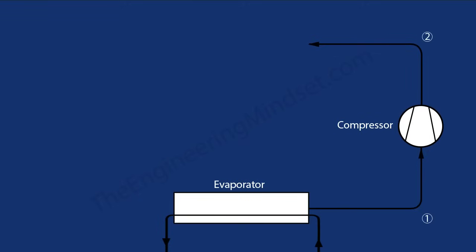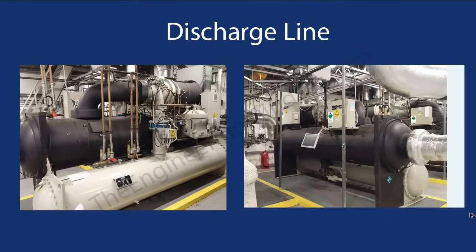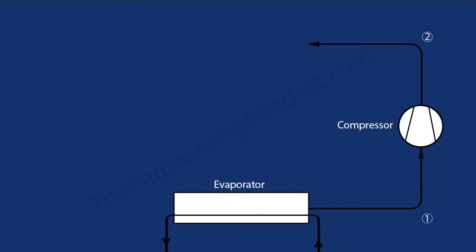As the refrigerant leaves the compressor it heads towards the condenser via what's known as the discharge line, which we'll refer to as Point 2 on the graphs. The discharge line is this pipe coming out of the compressor and heading down into the condenser. There's an isolating valve here so you can contain the refrigerant inside if you ever need to remove the compressor for maintenance.